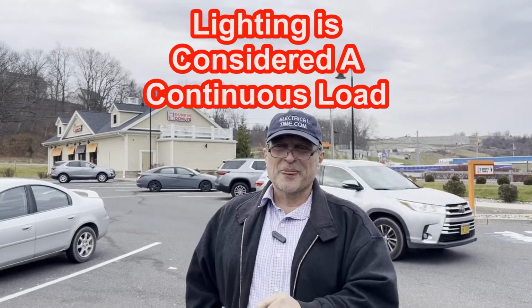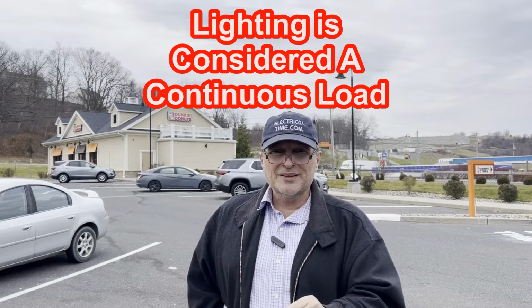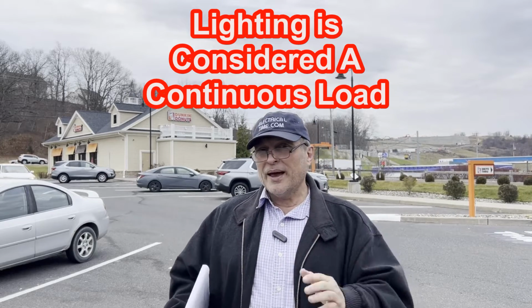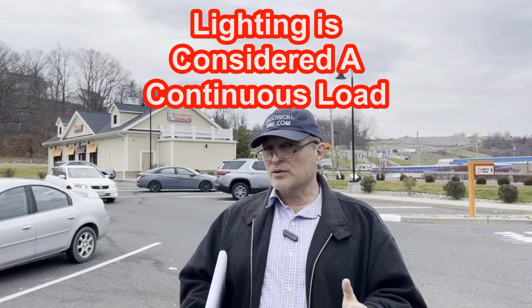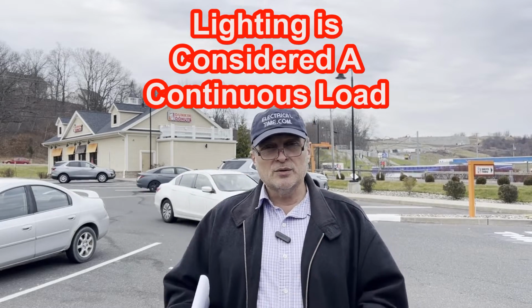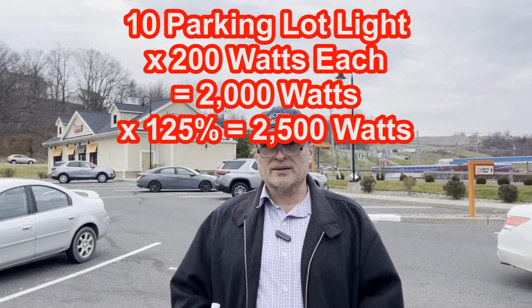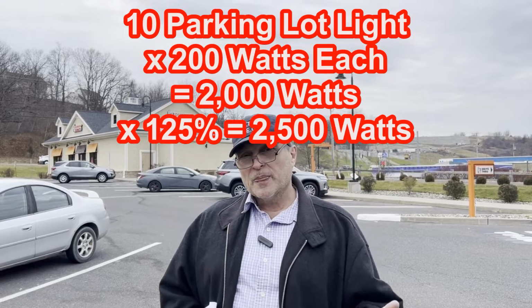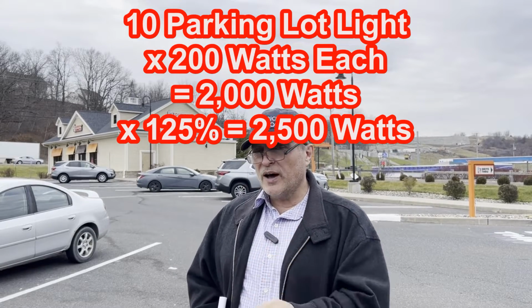That is correct. So we have a continuous load when the maximum ampacity is going to be on for 3 hours or more. So we're going to take that 2,000 watts times 125%. We're going to end up with 2,500 watts.